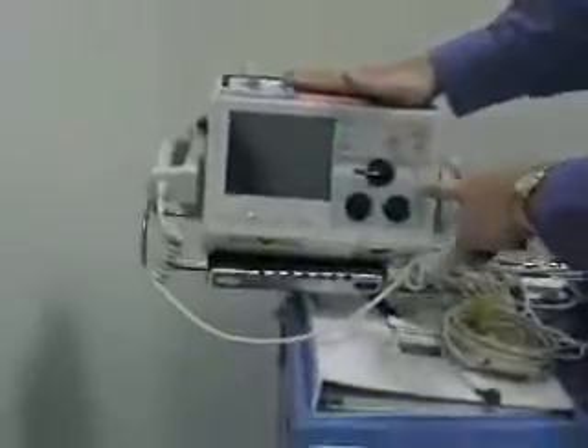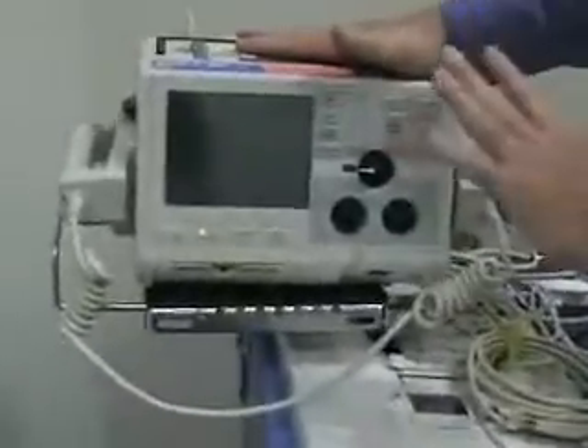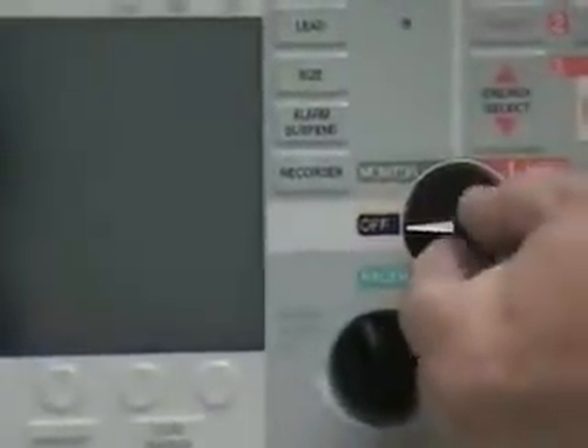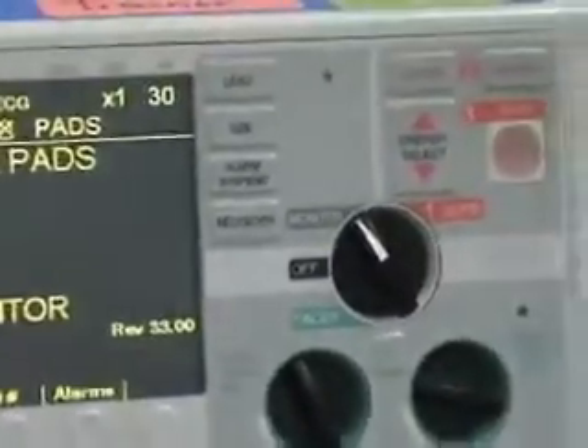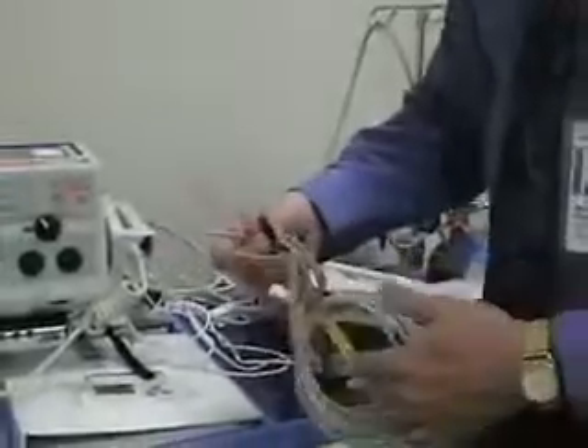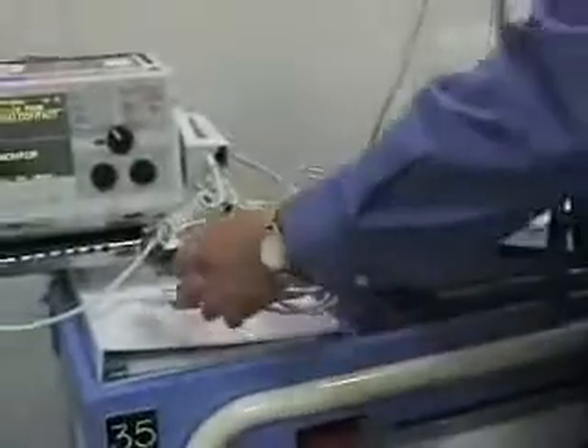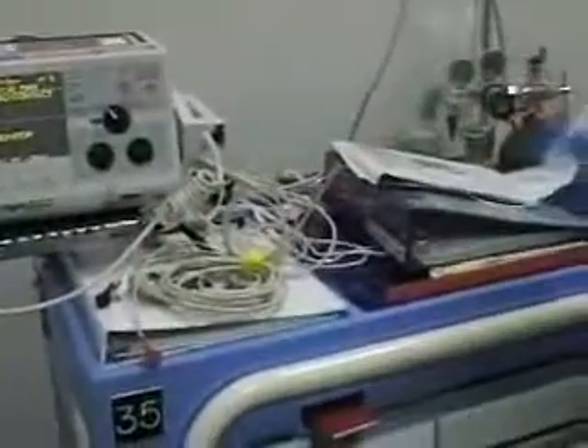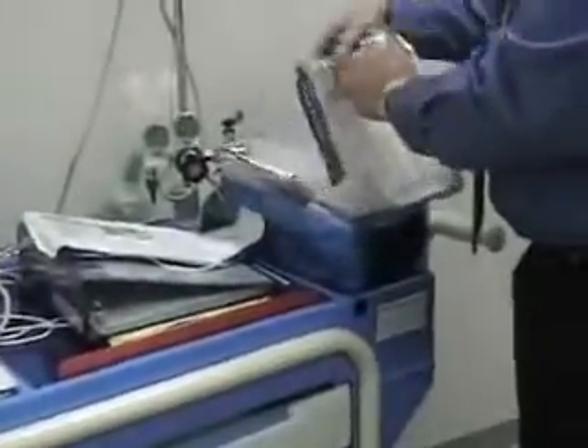The additional capability here is that you can use the defibrillator monitor simply as a monitor. You'll see here on the left side is one of your choices. Turn it to monitor, it will activate the machine, and now you can use this defibrillator monitor for telemetry purposes. You have a 3-lead cable for electronic monitoring. Most carts have additional electrodes stored, without having to open up the cart, so that you have easy access to be able to utilize that.